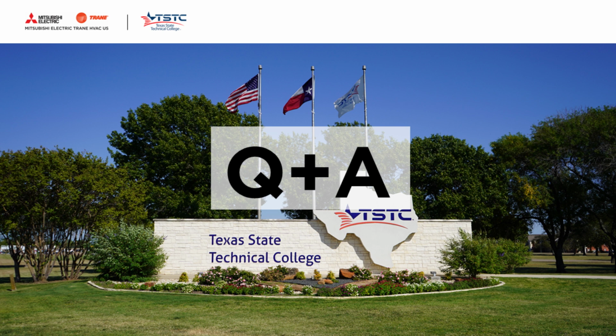So not only are you adding air conditioning, you can really deem that to be a strategic electrification project because you're able to really trim down the fossil fuel consumption of that existing boiler. I've had state universities or some larger private colleges talk about how they'd like to trim the consumption of their central plant. Same idea goes in that example. You could take a building that has a bad condensate return level, or simply the building that's the furthest away with the most pumping losses. Bring a VRF system to that specific building, and it's a very strategic electrification of the campus.